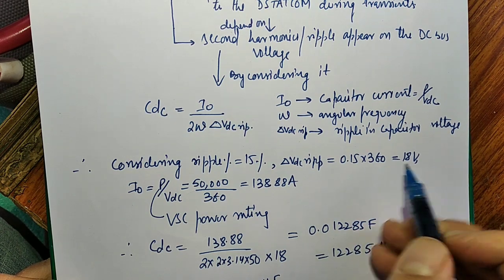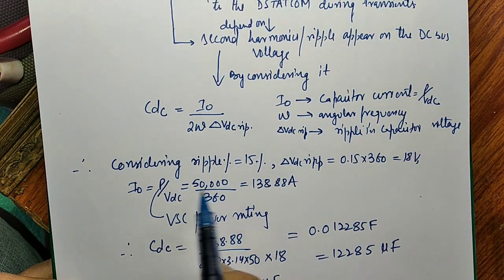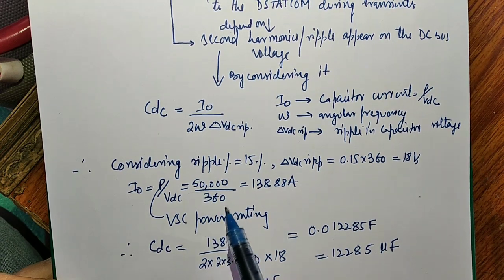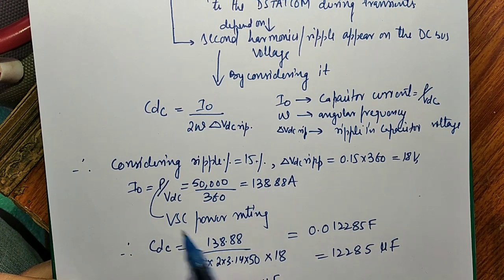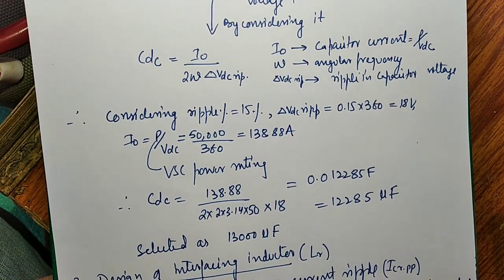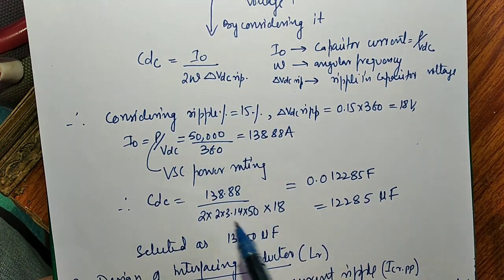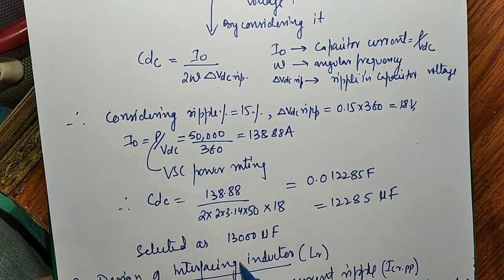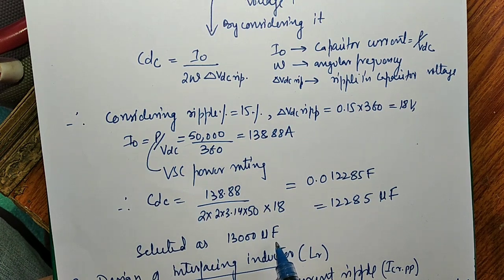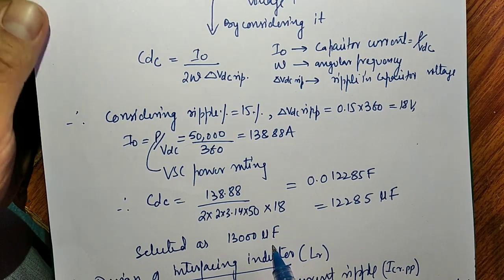We have taken the reference voltage of 360 V, giving ΔV_ripple of 54 V. Wait — delta V ripple is 0.15 × 360 = 54 V. For a 50 kVA system, I₀ equals 50,000 divided by 360, giving the DC capacitor current. After putting all these values into the capacitor equation, we get approximately 12,285 µF. We select 13,000 µF, or any nearby rating available in the market. For simulation purposes you can take any value, but we should use real values in simulation as well.